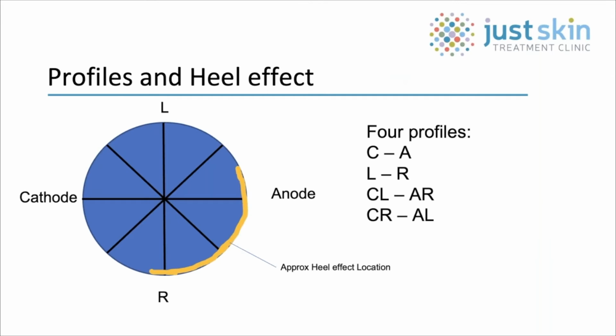The profiles for the largest field sizes were the most heavily scrutinized. The heel effect was not apparent on field sizes 10 centimeters and below. The results in the next slide were taken using a piece of EBT3 film with a 3-minute beam delivery. The only practical change this made was for the therapists to direct the anode end of the beam to overshoot the patient where possible, which is good practice for all energies when using large fields.